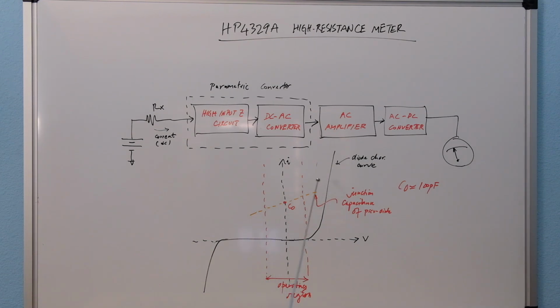As you increase the bias, its capacitance increases, and as you decrease the bias negatively, it decreases. Using that principle, it creates an imbalance in the bridge, and then that signal is converted to an AC signal, which is amplified and converted to DC, eventually displayed as a resistance indication. So this is a diode characteristic, as you can see here.